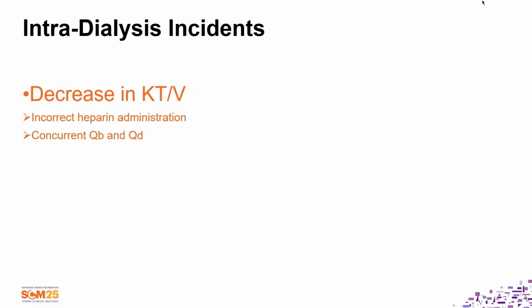But back in the Stone Age where we were cranking our own machines, when I started dialysis, there was no color coding. And actually, this occurred quite frequently where we had both dialysate flow and blood flow going the same way. Now, there is actually a use of concurrent QB and QD. One of my physicians asked, we're clearing the patient, how do we slow down the clearance? If you run both flows, blood flow and dialysate flow, in the same direction, you actually decrease clearance by almost 37%. So if pulling off too much, shifting, is a problem, my physicians have ordered this.